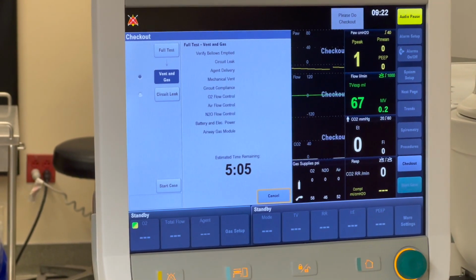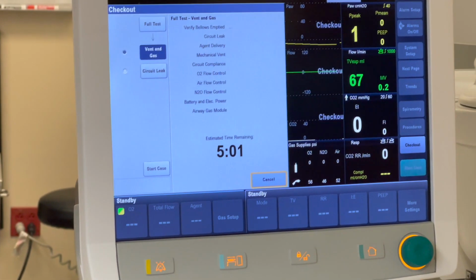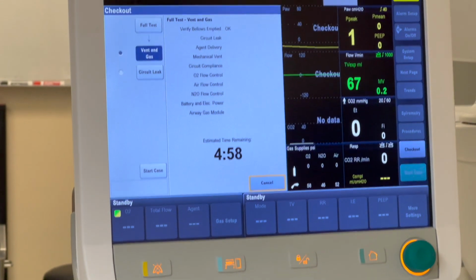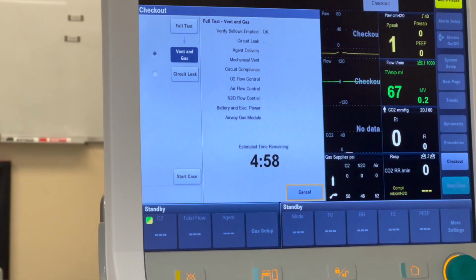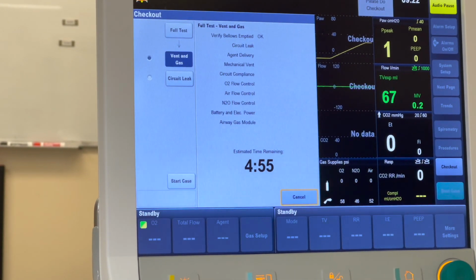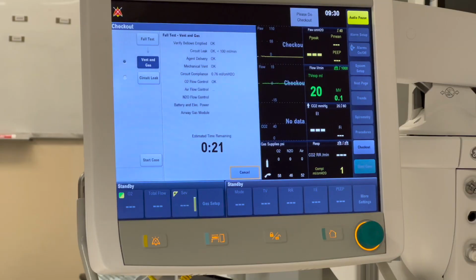Now this step takes about 5 minutes, so we are going to fast forward through all of this and show you what the end results look like. But as you can see, it's going to check several different major components: the circuit, agent delivery, circuit compliance, O2 flows, battery power, and airway gas modules. As the vent and gas test nears completion, we can see that we've successfully checked many of these components. And the next screen should pop up pretty soon and give you instructions for the next portion of the circuit leak test.